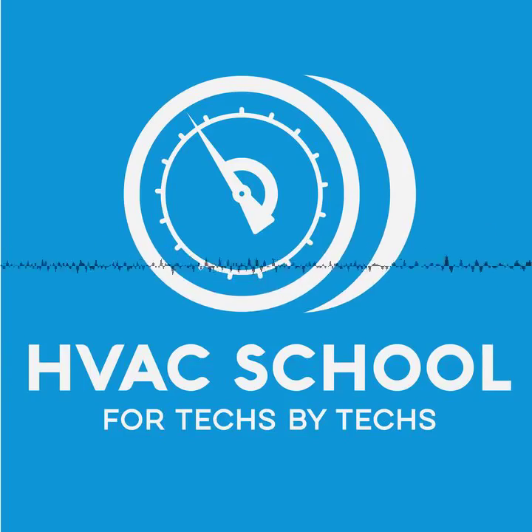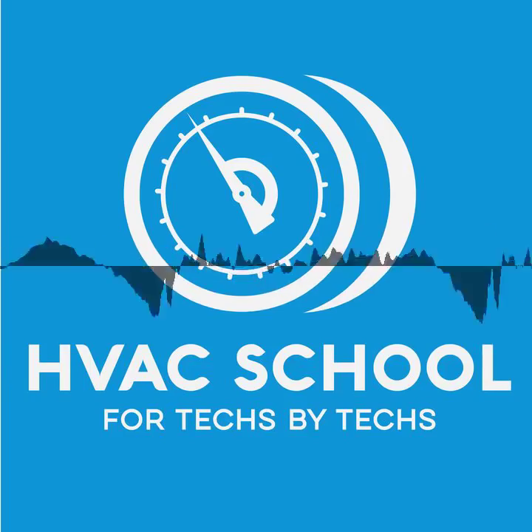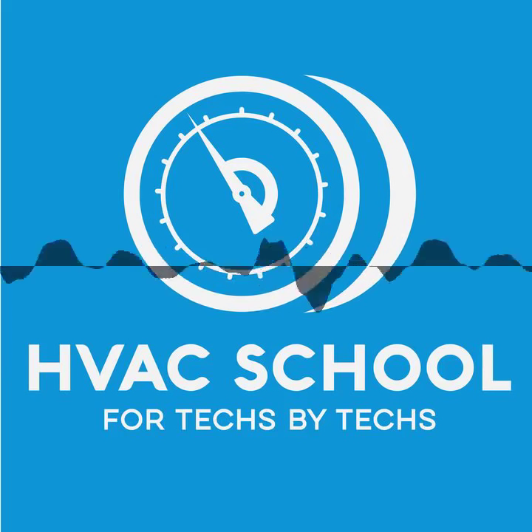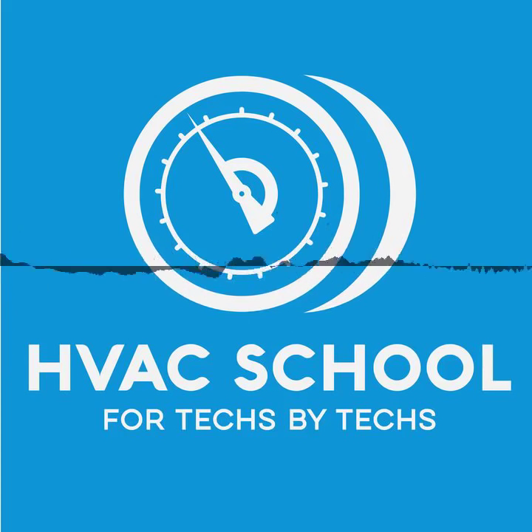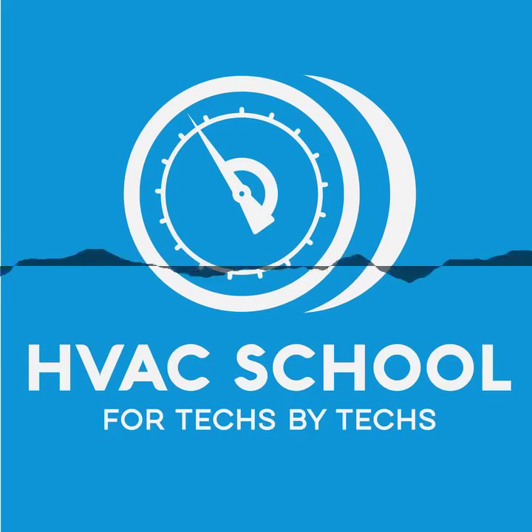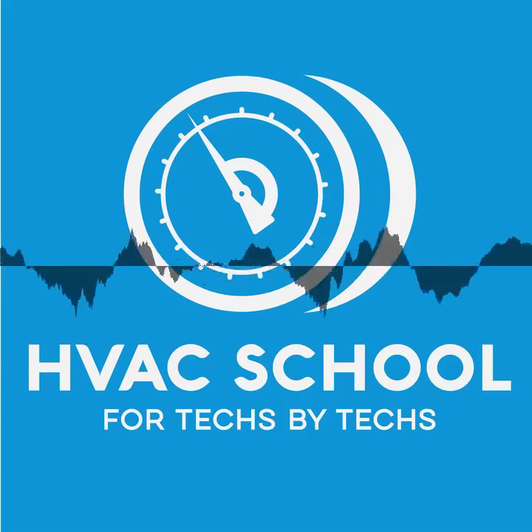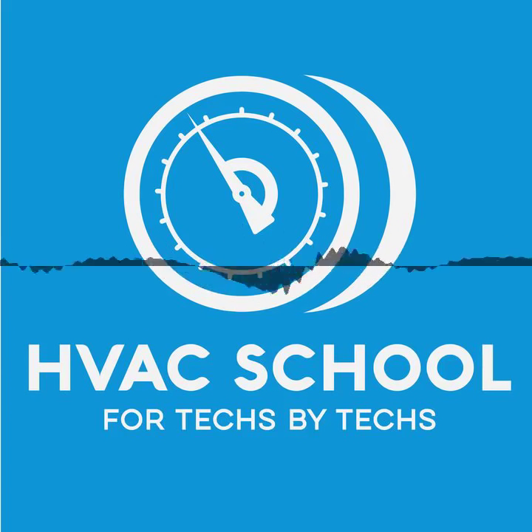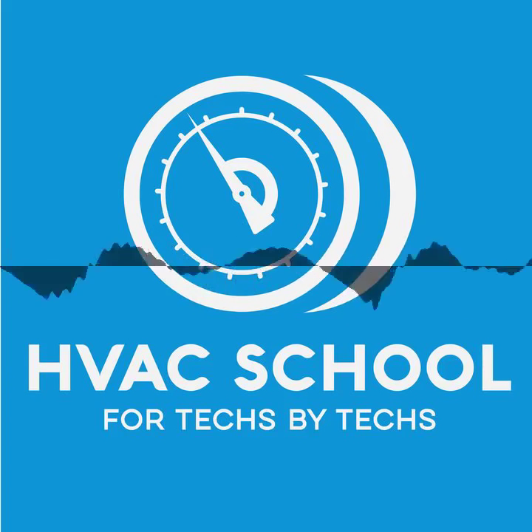Hopefully below 61 degrees. No, not below 61 degrees. The refrigerant being below 61 degrees as it's entering that compressor? Or Copeland will find you. I think it's 65. I respect that. So yes, Copeland recommends, and correct me if I'm wrong, but I believe it's 65 degrees. They want the refrigerant to be less than that on a typical high temp air conditioning application in order to properly cool the compressor. But even more important than the temperature of the refrigerant is the density of the refrigerant.